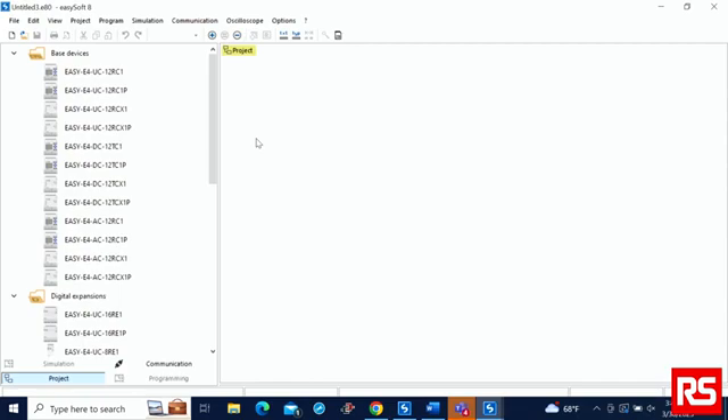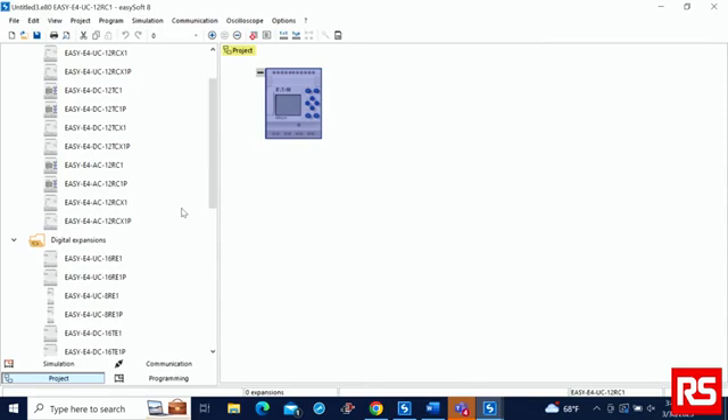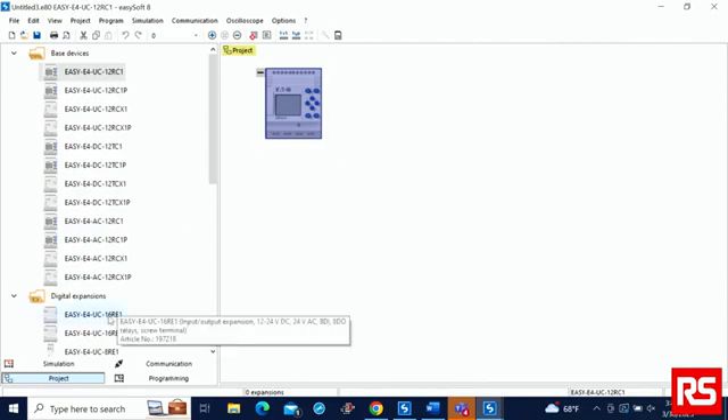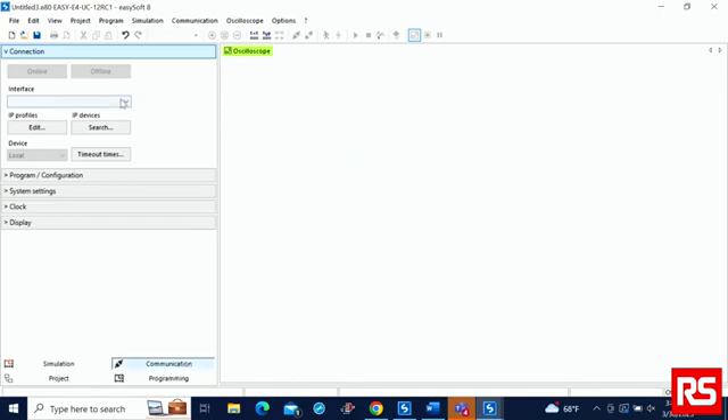Now we will do a quick overview on the software environment. First, drop in the Easy E4 model that you are using, then select the firmware version that you are using. Next, go ahead and add a digital expansion module. To connect to the Easy E4, go over to Communications, then go to Interface and select a PC port that is currently connected to the Easy E4. You can go to IP Profiles to configure the IP address on the Easy E4, and then go to the Clock section to input your device time.